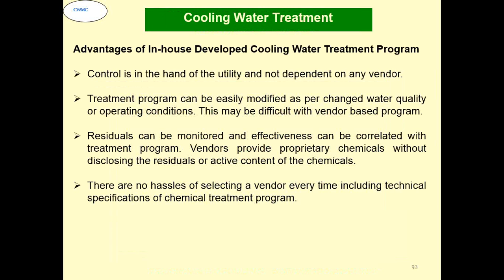Normally there are many modes of doing cooling water treatment. Generally people employ a vendor to do the chemical treatment at their units or industry. But we have found there is an advantage if we do our own cooling water treatment program development, because the control is totally in your hand and not dependent on any particular vendor. The treatment program can be easily modified as per changes in water quality or operating conditions, which may be difficult with a vendor-based program. Residuals can be monitored and effectiveness can be correlated with the treatment program. Vendors provide proprietary chemicals without disclosing the residuals or active content of the chemicals. There are no hassles of selecting a vendor every time, including technical specifications or chemical treatment program, etc.